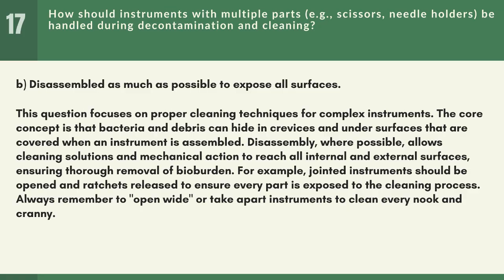This question focuses on proper cleaning techniques for complex instruments. The core concept is that bacteria and debris can hide in crevices and under surfaces that are covered when an instrument is assembled. Disassembly, where possible, allows cleaning solutions and mechanical action to reach all internal and external surfaces, ensuring thorough removal of bioburden. For example, jointed instruments should be opened and ratchets released to ensure every part is exposed to the cleaning process. Always remember to open wide or take apart instruments to clean every nook and cranny.